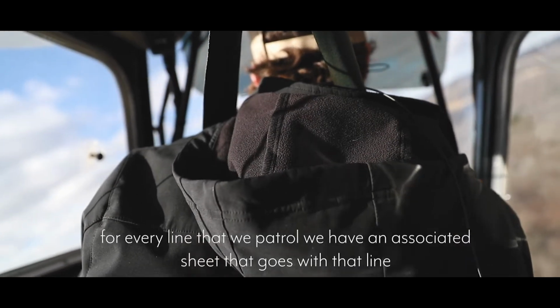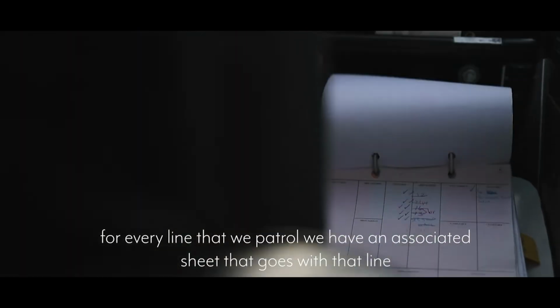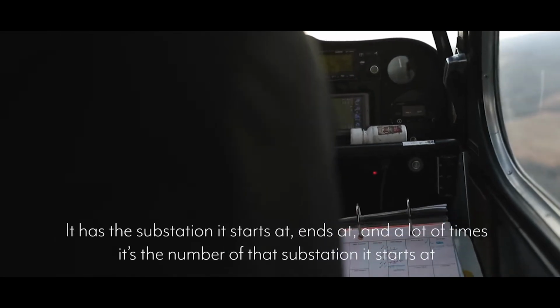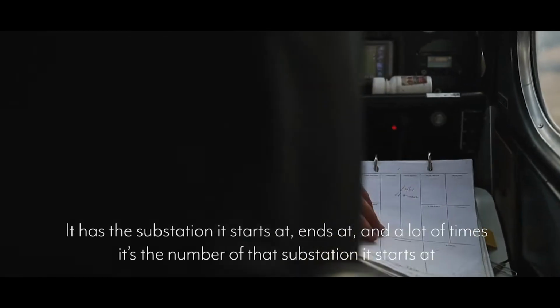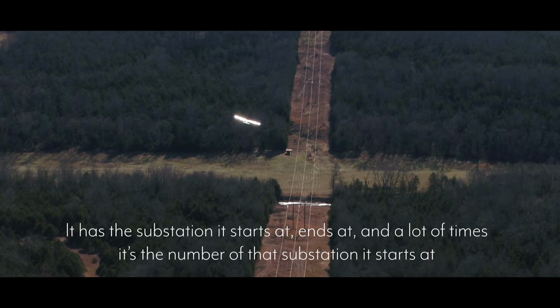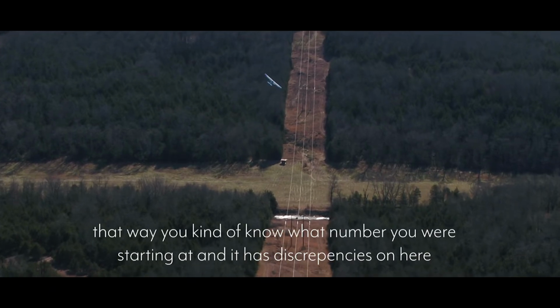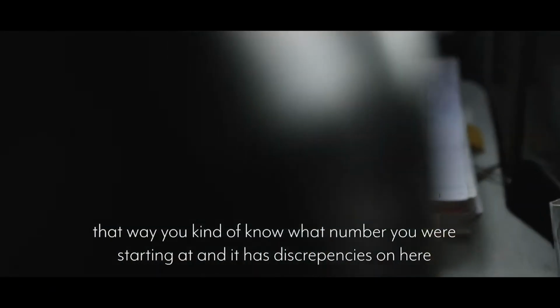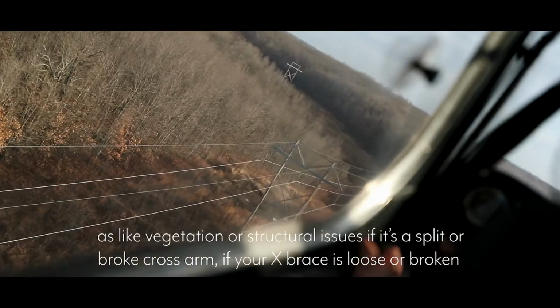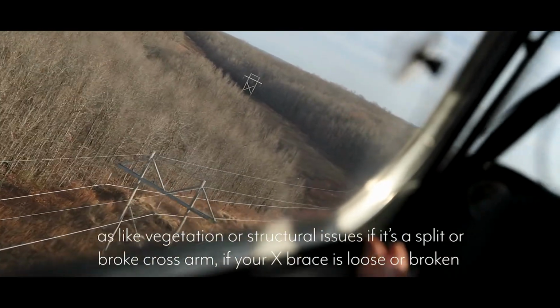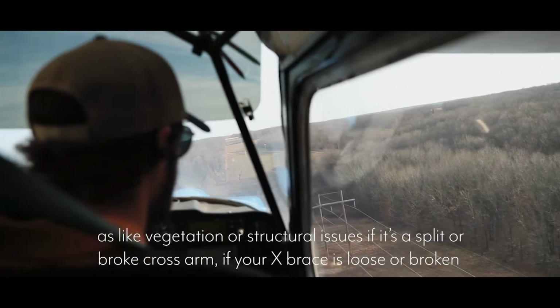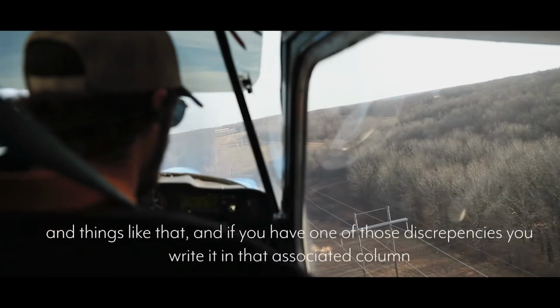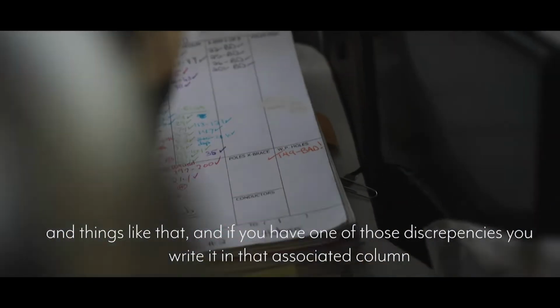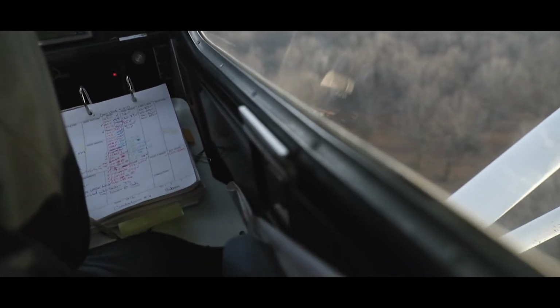For every line that we patrol, we have an associated sheet that goes with that line that has the substation it starts at and ends at, and a lot of times the number at that substation it starts at, so you know what number you're starting at. It has discrepancies listed like vegetation or structural issues, a split or broken cross arm, a loose or broken X-brace, and things like that. If you find one of those discrepancies, you write it in that associated column.